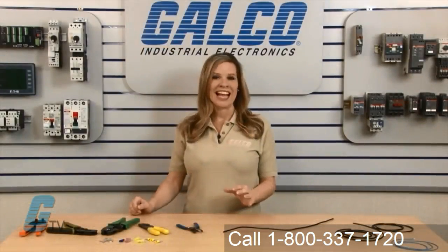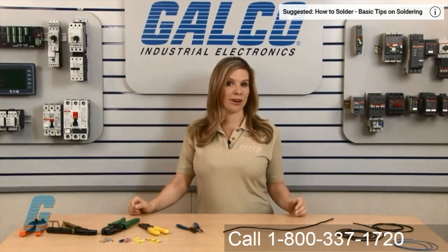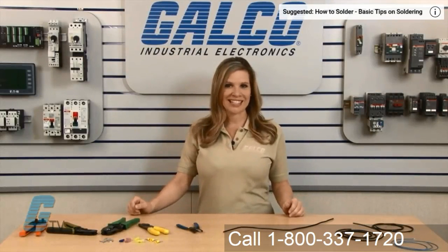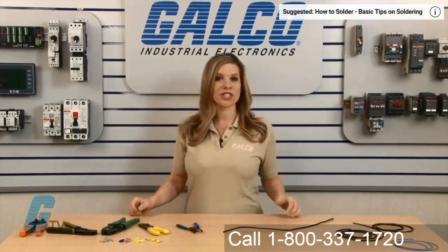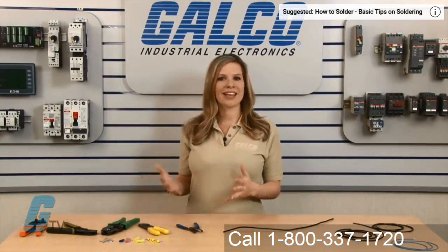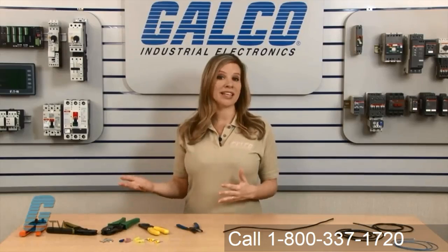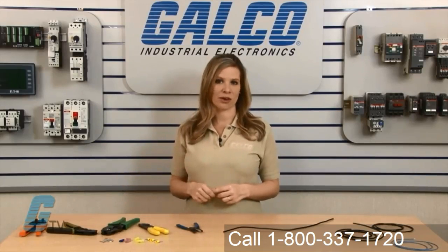A poor crimp can leave air pockets between the wire and connector. These air pockets can allow moisture to collect, resulting in eventual corrosion and ultimately leading to connection failure.